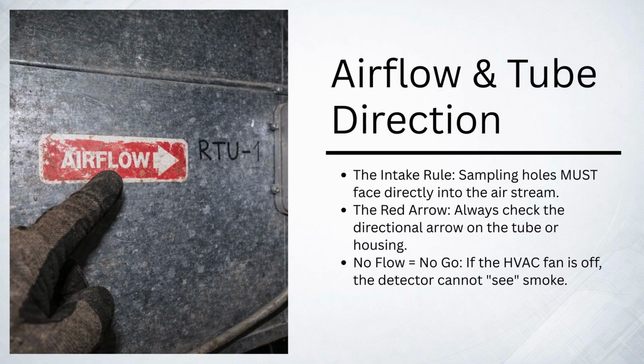This brings us to the science: differential pressure. Duct detectors rely entirely on air velocity. If the HVAC fan is off, or if the belt is broken, the detector will not work because no air is being pushed into the sampling tube. To work correctly, there must be a pressure difference between the intake and exhaust. Manufacturers specify a range of acceptable airflow, usually between 300 and 4,000 feet per minute. If the air is moving too slow, it won't enter the tube. If it's moving too fast, it creates turbulence.